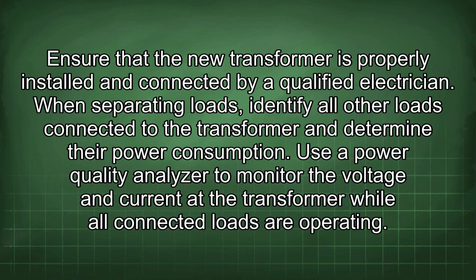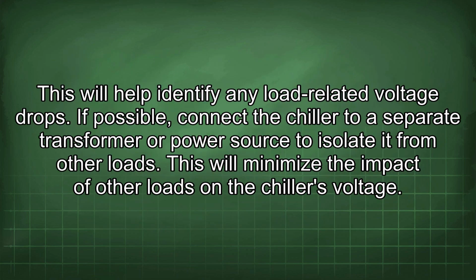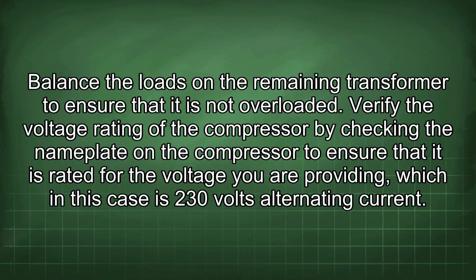When separating loads, identify all other loads connected to the transformer and determine their power consumption. Use a power quality analyzer to monitor the voltage and current at the transformer while all connected loads are operating. This will help identify load-related voltage drops. If possible, connect the chiller to a separate transformer or power source to isolate it from other loads. This will minimize the impact of other loads on the chiller's voltage. Balance the loads on the remaining transformer to ensure that it is not overloaded.